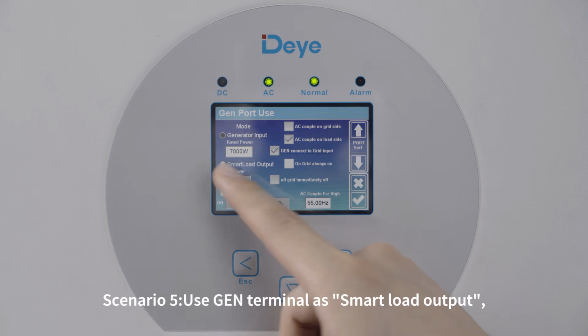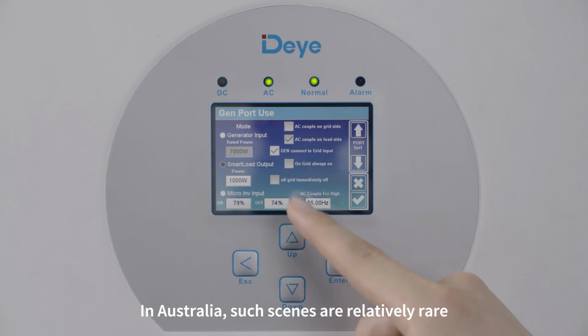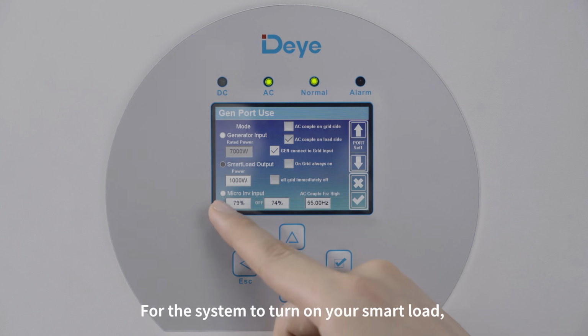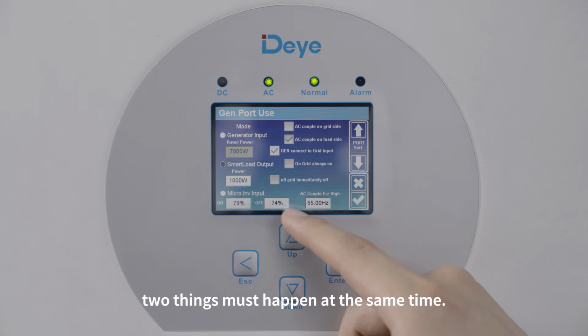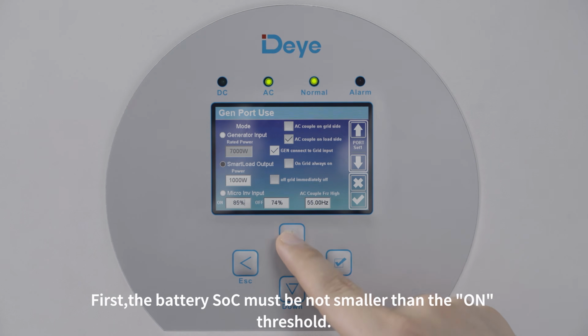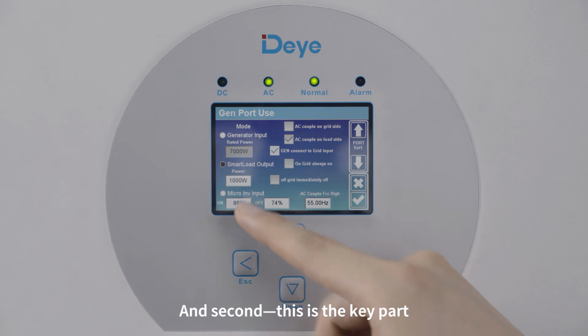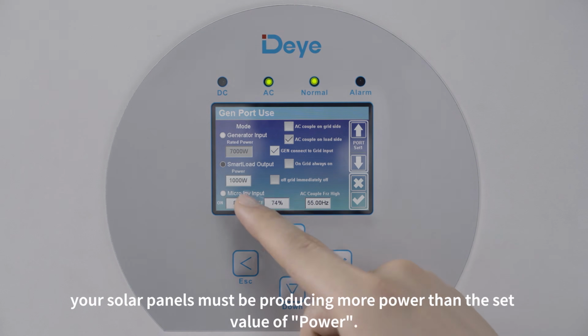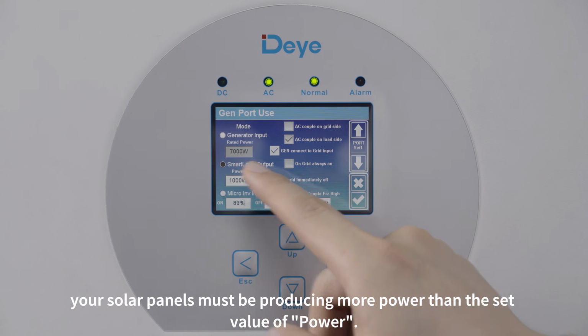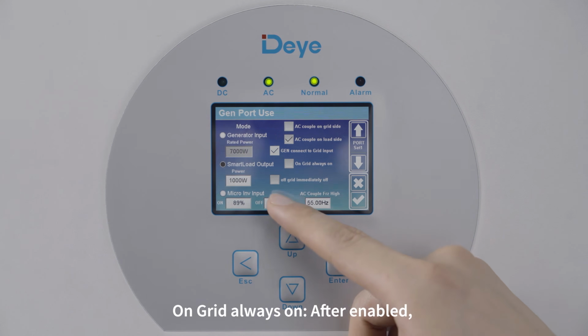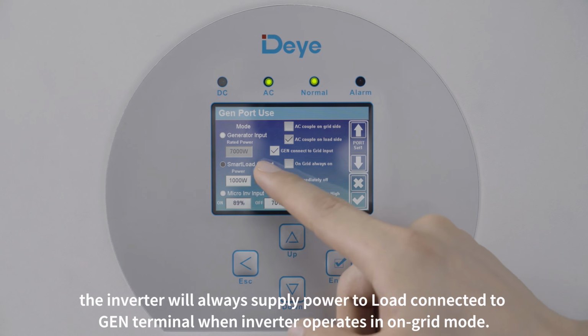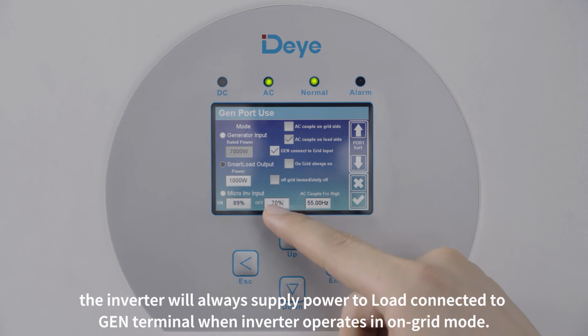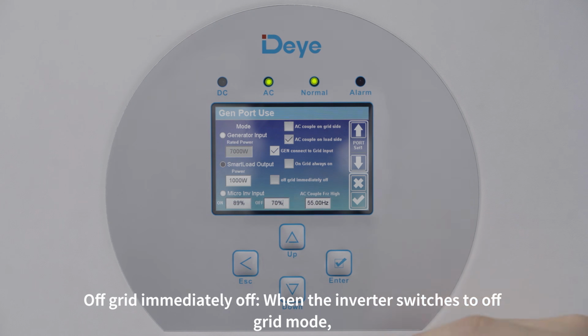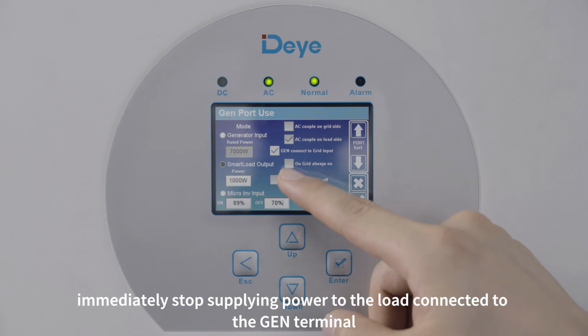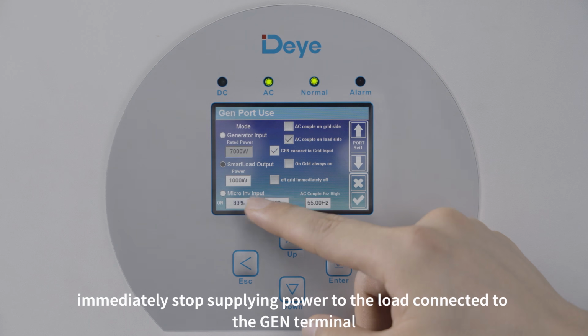Scenario 5. Use the GEN terminal as smart load output. In Australia, such scenes are relatively rare. For the system to turn on your smart load, two things must happen at the same time. First, the battery SOC must be not smaller than the ON threshold. And second, this is the key part, your solar panels must be producing more power than the set value of power. On-grid always on: after enabled, the inverter will always supply power to the load connected to the GEN terminal when the inverter operates in on-grid mode. Off-grid immediately off: when the inverter switches to off-grid mode, it immediately stops supplying power to the load connected to the GEN terminal.